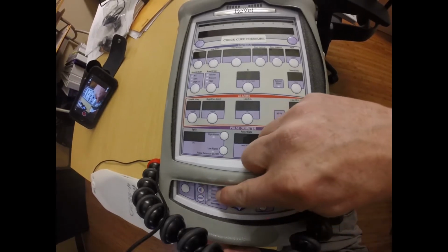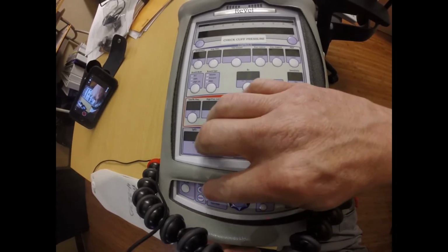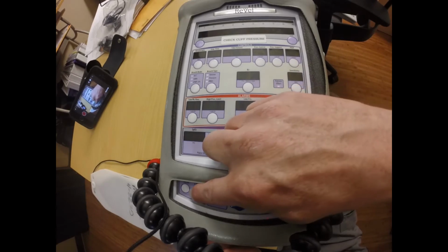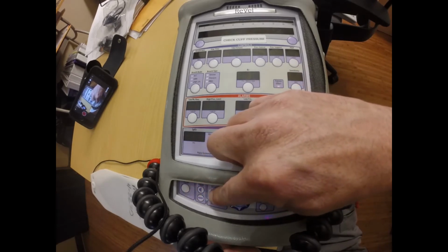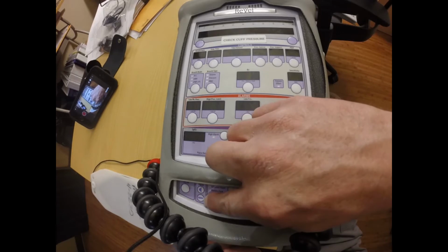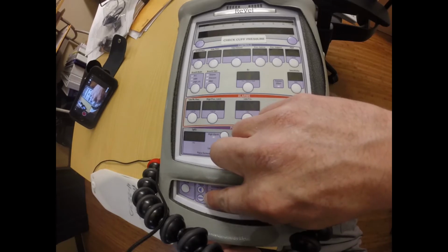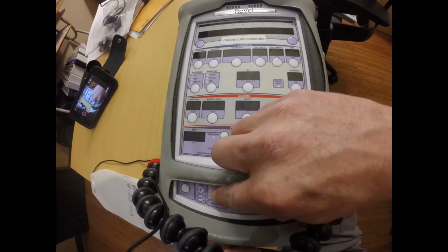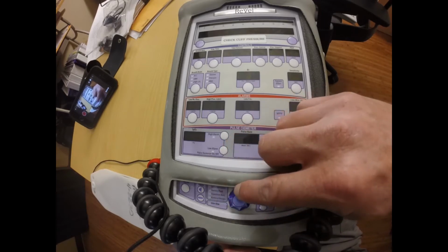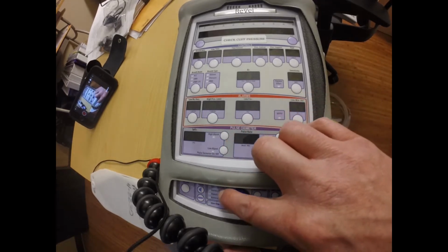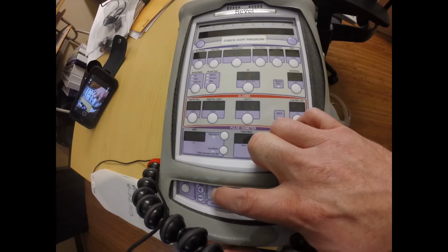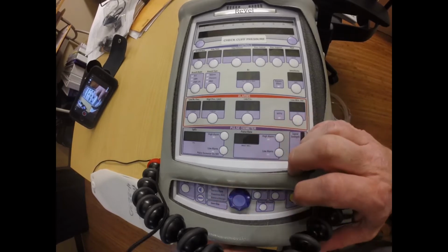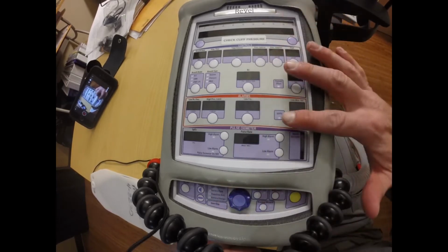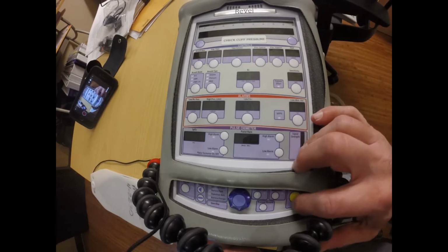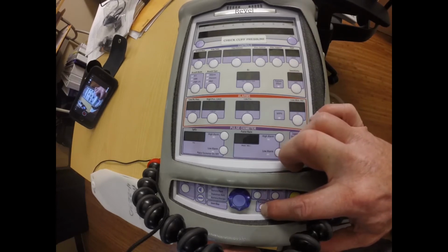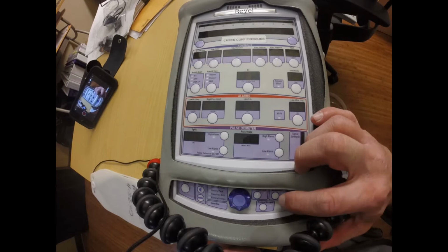Down below the pulse oximetry panel here, there's some very important buttons. The first is the on-off, of course. The other is an alarm check, so you can adjust the volume with that and see what it's at. You'll be able to see what power source you are using with this panel right here will illuminate. You can lock the entire thing if you wish by pushing in that button. You can give a manual breath to your patient at any point by pushing in that button.